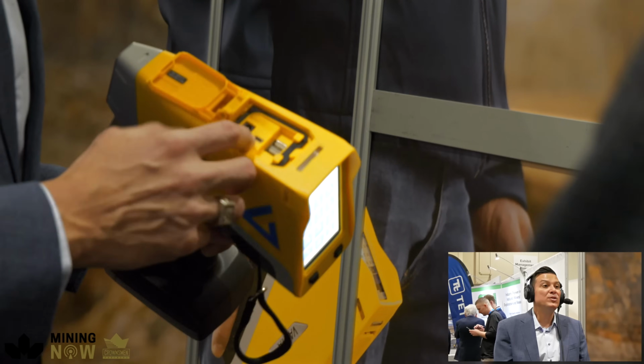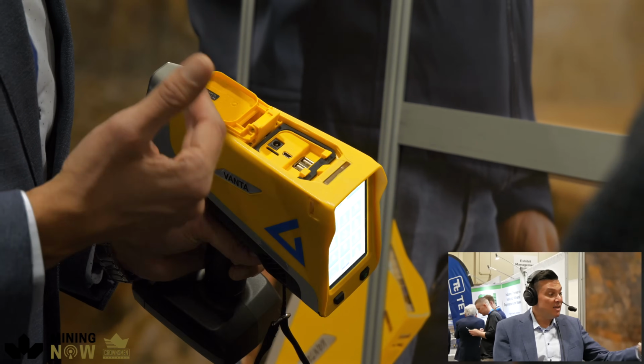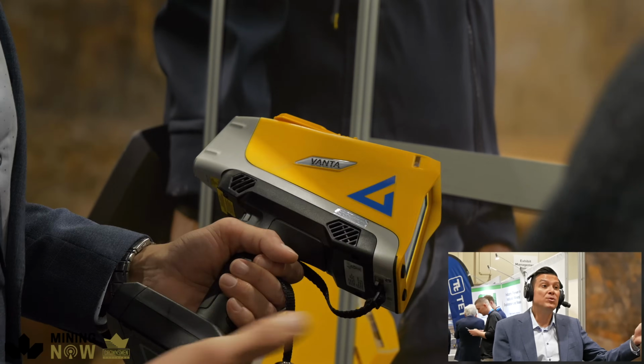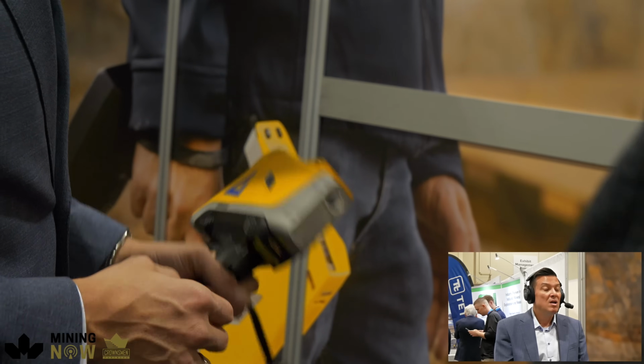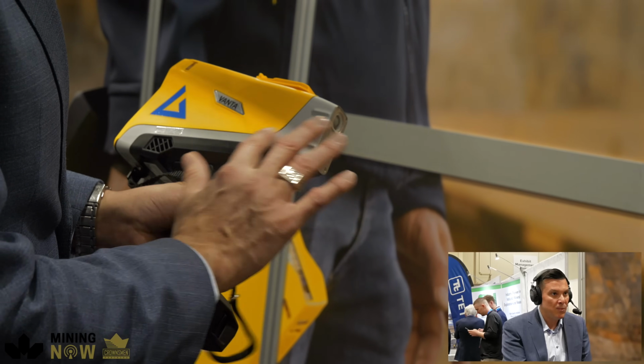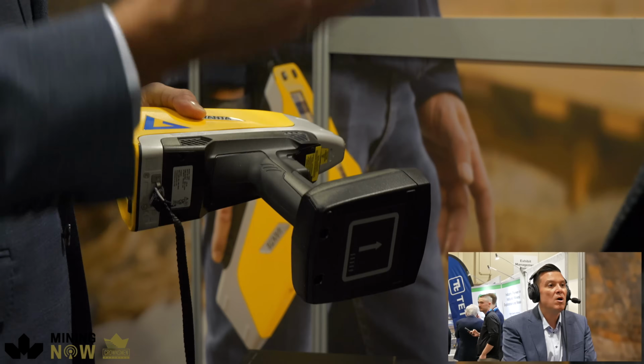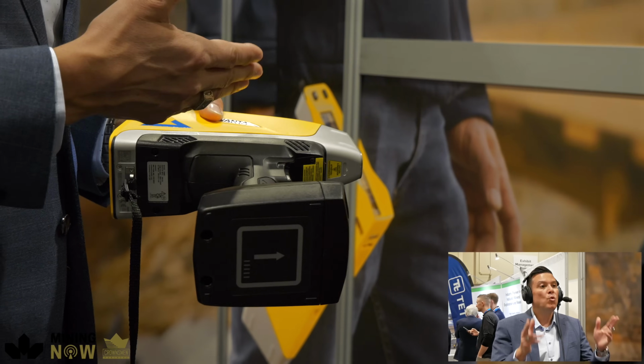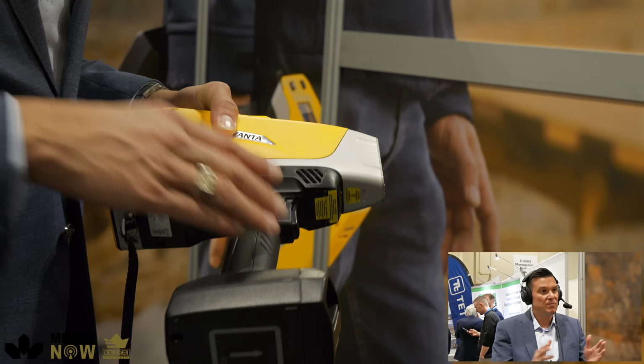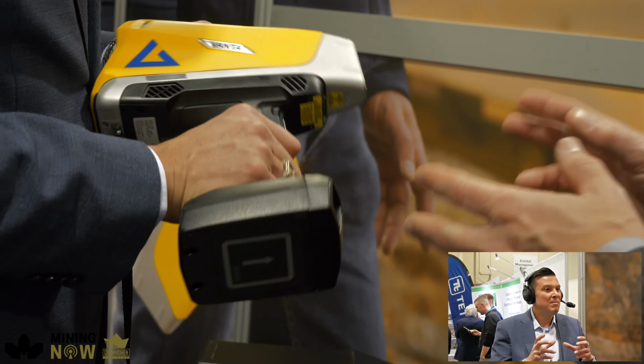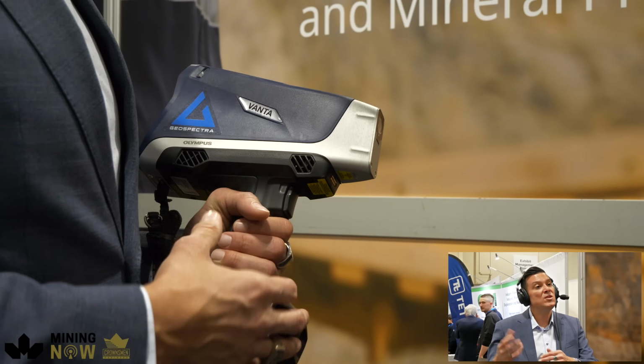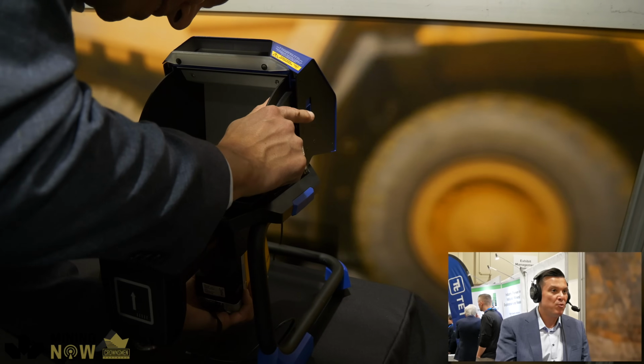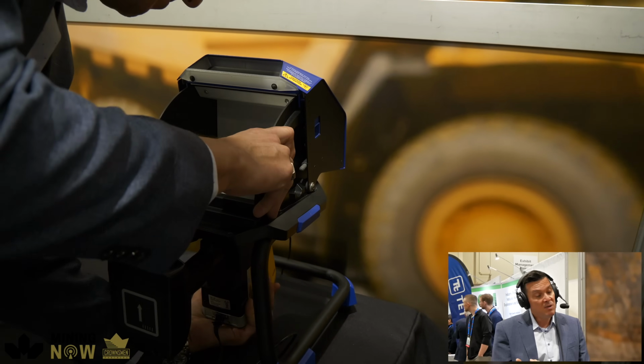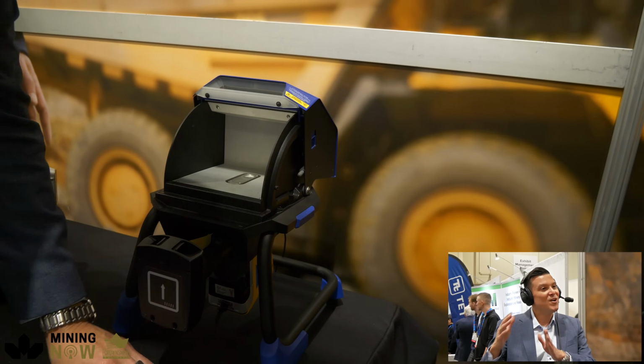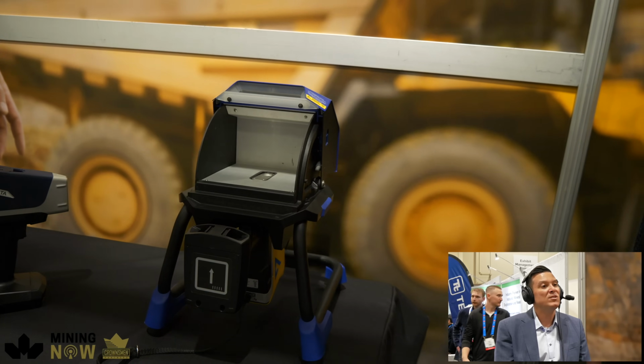Absolutely, so in the machine we have a tube that produces an X-ray. The VantaMax 55 kV will produce an X-ray at 55 kilovolts. That will excite the sample, and the excitation will come back to a detector. We'll be reading that excitation, and then we do some complicated math, and we're able to give you the percent of that element present. With the 55 kV, we can give you the rare earths percentage at a very low level of detection.